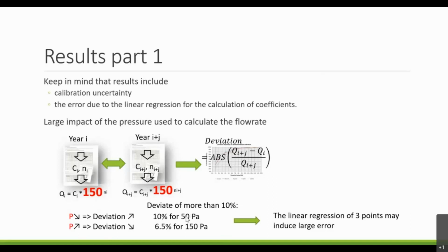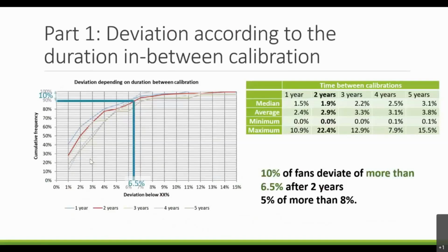If we were using only 50 Pascal, we found out that 10% of fans were deviating by more than 10%. While if we are using 150 Pascal, which is more or less the average pressure at the fan, it's only 6.5% that deviate by more than 10%. So the linear regression with only 3 points may also induce a large error in this study. So as I said, in the first part of the study, we found out that 10% of fans deviate by more than 6.5% after 2 years, and 5% of fans deviate by more than 8% after 2 years.